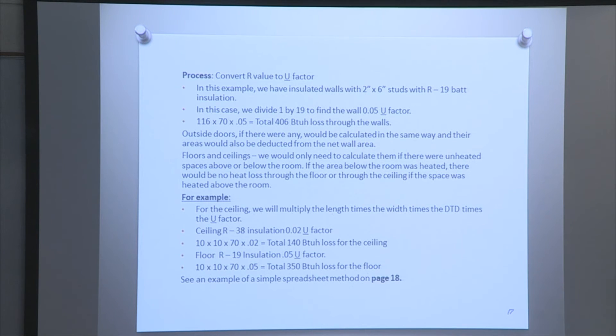Here's an example of the simple spreadsheet. You can see where we calculated the DTD — indoor design temperature minus outdoor design temperature — equals 70 degrees. For bedroom number one with two exposed walls: infiltration heat loss was 1,008 BTUs; window conductive heat loss was 1,078 BTUs; wall heat loss was 406 BTUs; ceiling heat loss was 140 BTUs; floor heat loss was 350 BTUs. The total heat loss for that room is 2,982 BTUs. Dividing by 600 gives 4.97, so rounding up, you need a 5-foot section of copper fin tube baseboard for that room.